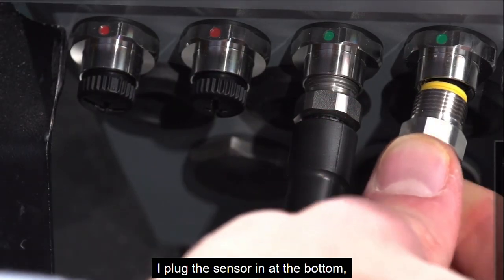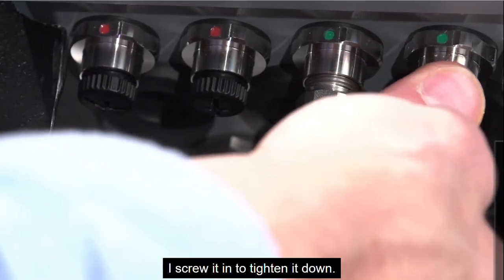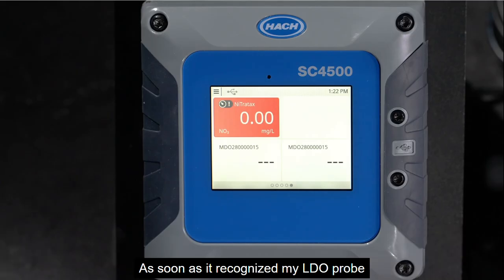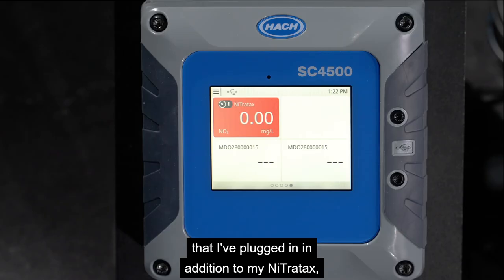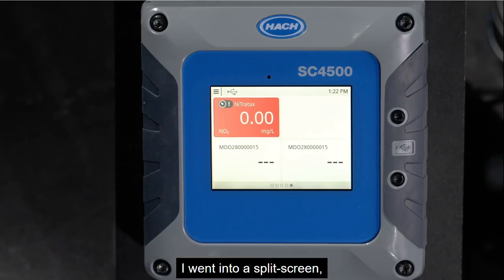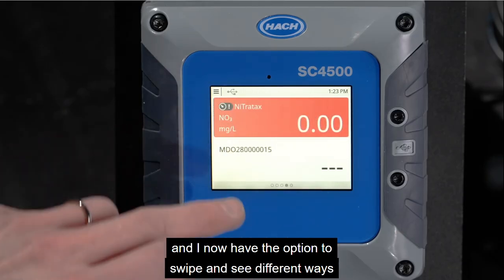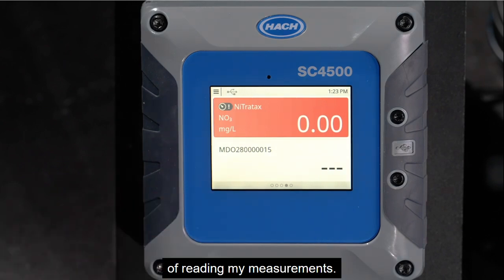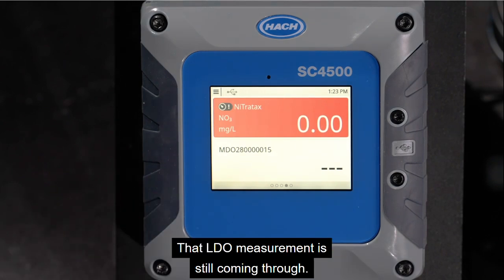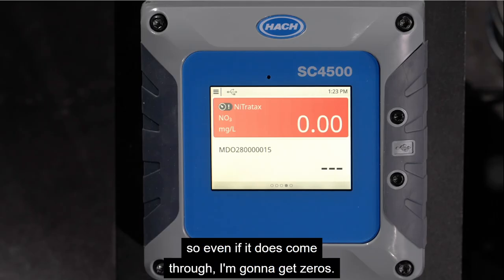Just like before, I plug the sensor in at the bottom and screw it in to tighten it down. You can see what happened on the screen. As soon as it recognized my LDO probe plugged in addition to my Nitratax, I went into a split screen, and now I have the option to swipe and see different ways of reading my measurements. That LDO measurement is still coming through, but I don't have it installed on anything, so even if it comes through, I'm going to get zeros.